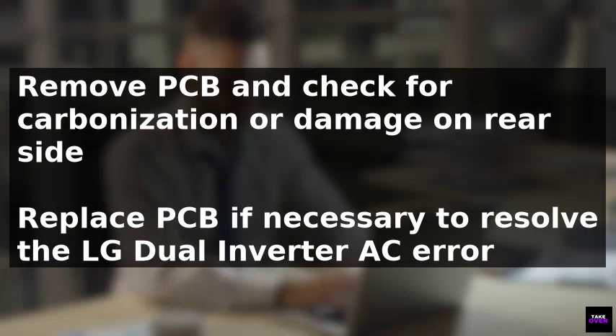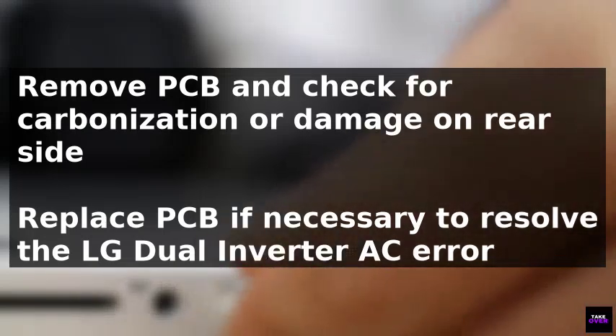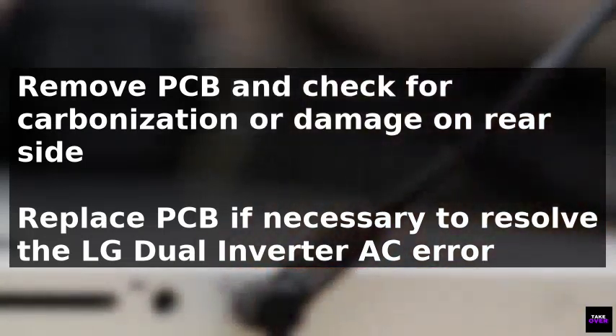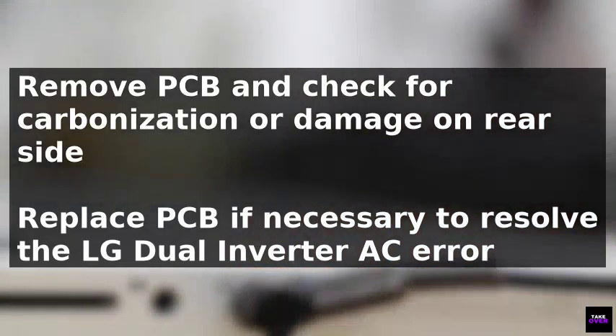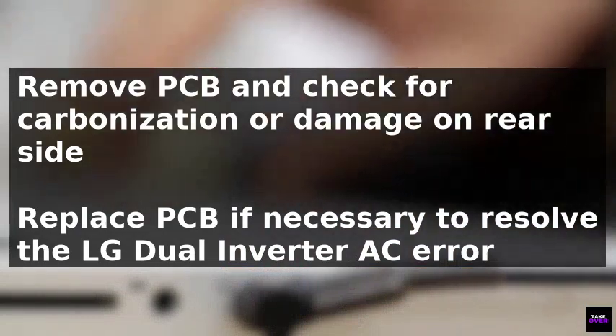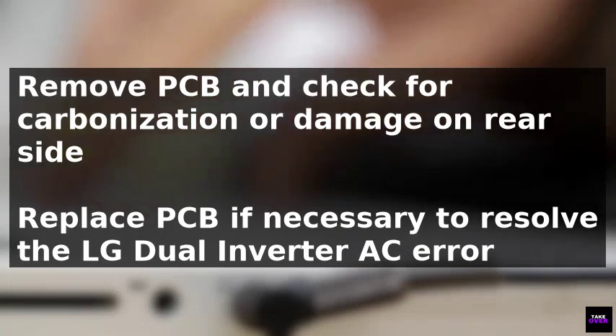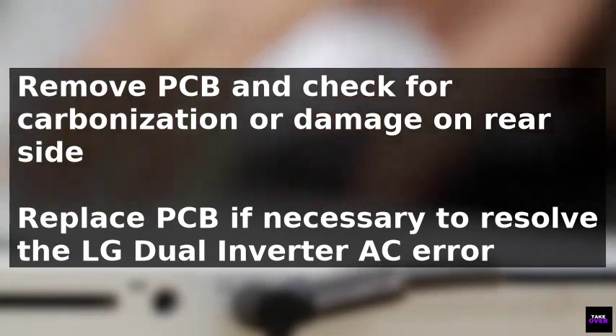Normal readings are DC 310V and 15 volts across terminals 1 and 5 against 4, respectively. Remove the PCB and check for carbonization on its rear side, inspecting for any damage or issues. If necessary, replace the PCB to resolve the error.